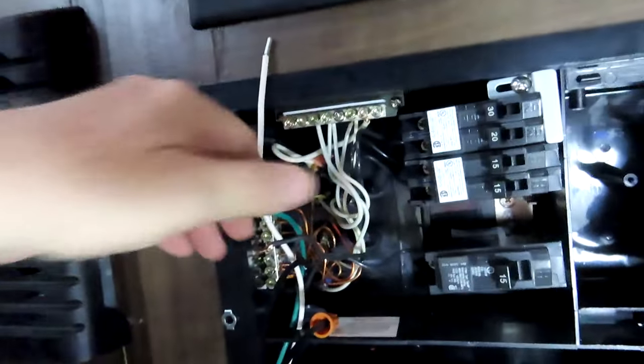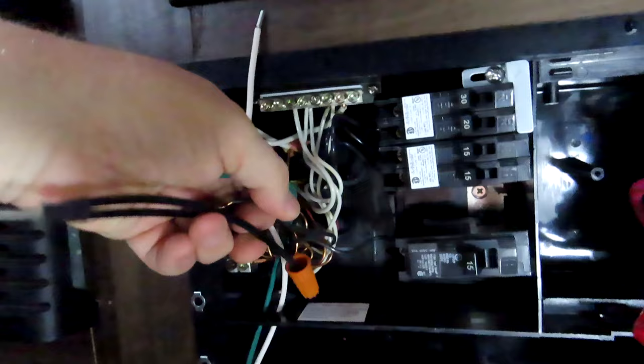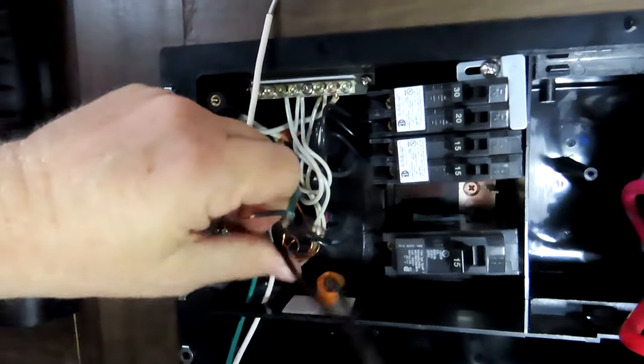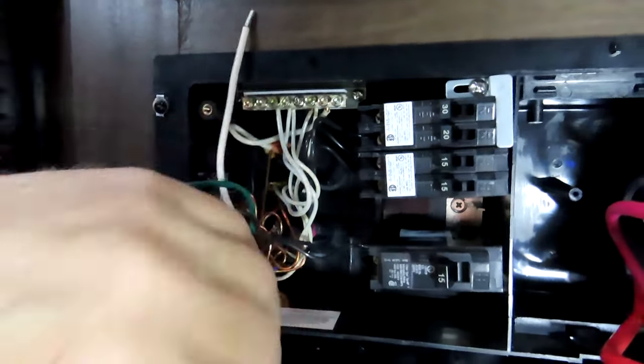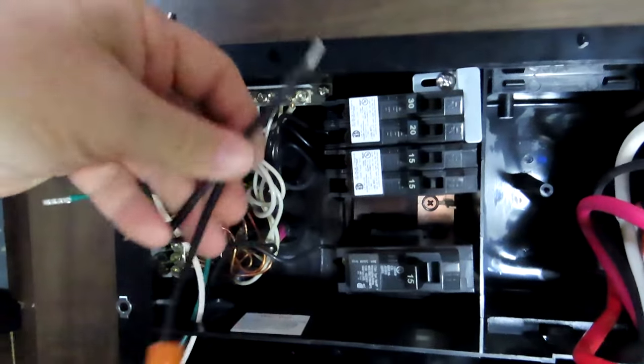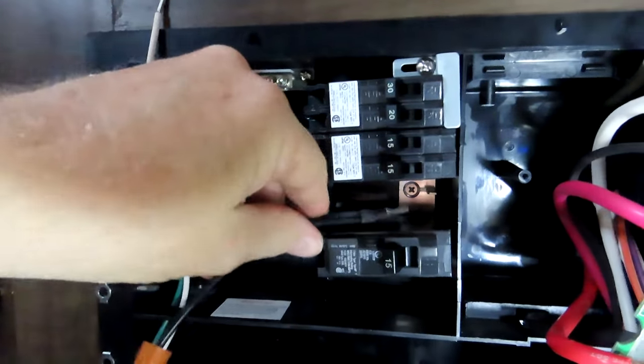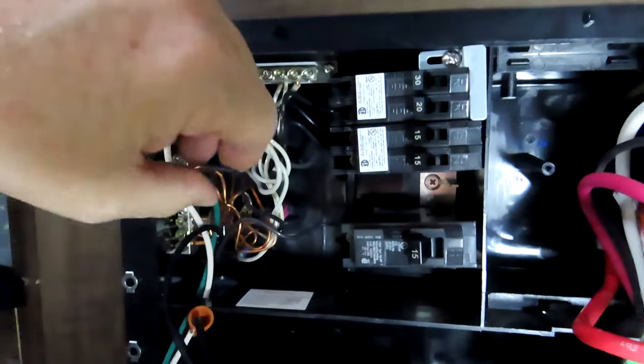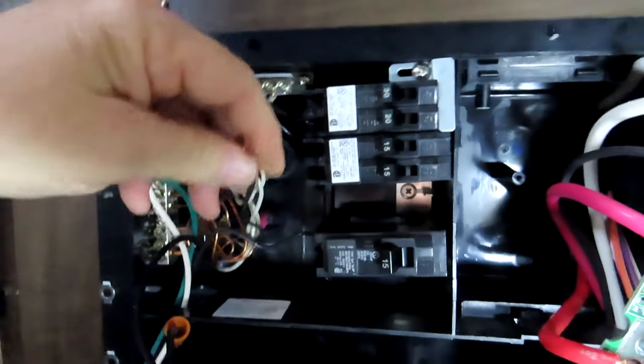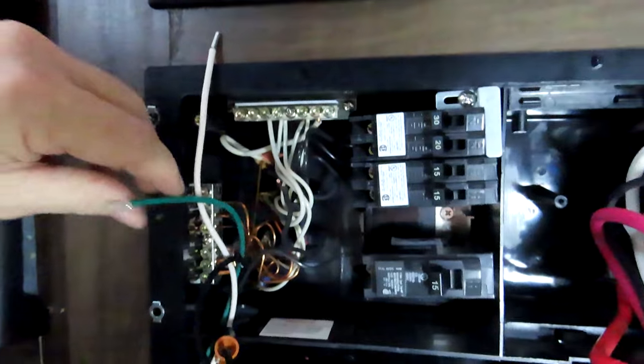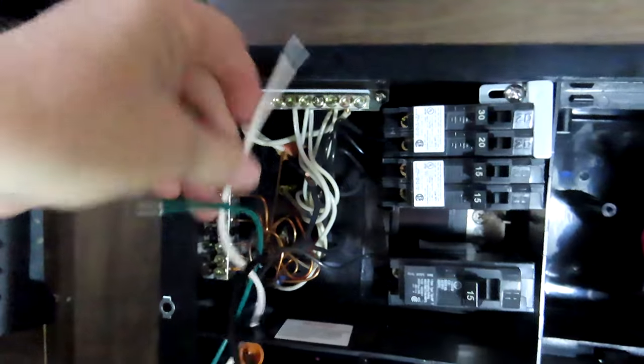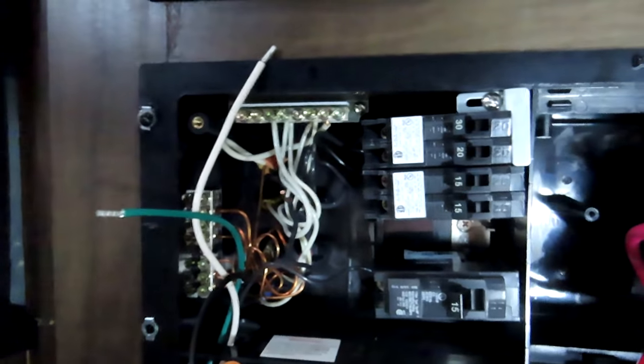Now we gotta hook up the power wires to the main power. And these are pretty easy. This one with the little thing on it goes to the breaker, so put that on the breaker. And the green goes with the copper grounds and the white goes with all the other whites, so no big deal.